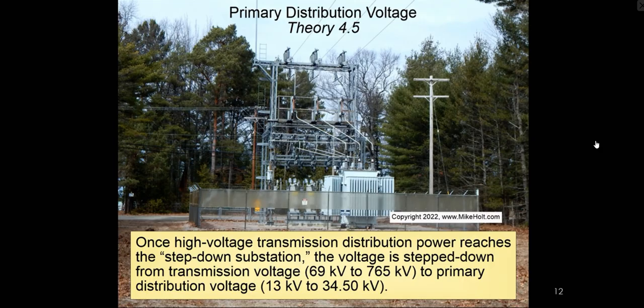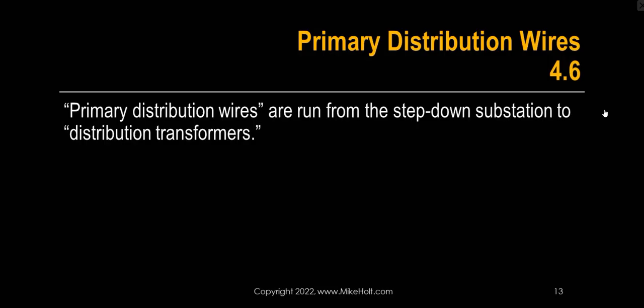So once high voltage transmission distribution power reaches the step-down substation, the voltage is stepped down from transmission voltage, maybe 69,000 to 765,000 volts (kV), to primary distribution voltage of 13 kV to 34.5 kV. Primary distribution wires are run from the step-down substation to distribution transformers.